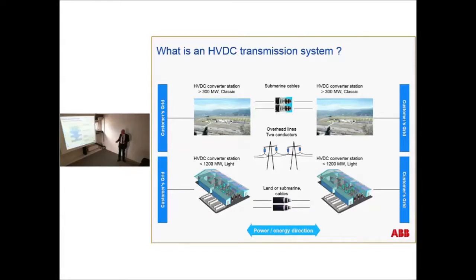Another advantage is that if you have a disturbance in that network, that disturbance will affect the voltage and the variations here, but that will not be transmitted to the other network. The DC link acts as a firewall between the systems. And since we can control the power, we can also support a weak network with the HVDC link, especially during disturbances, by modulating the power energy input and the voltage in the weak system.